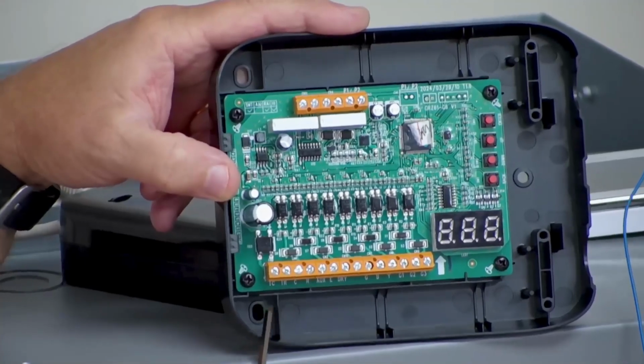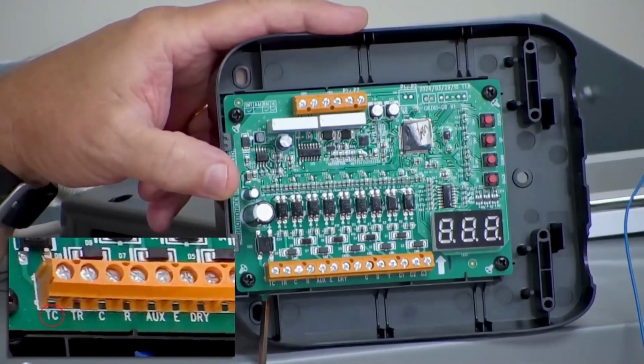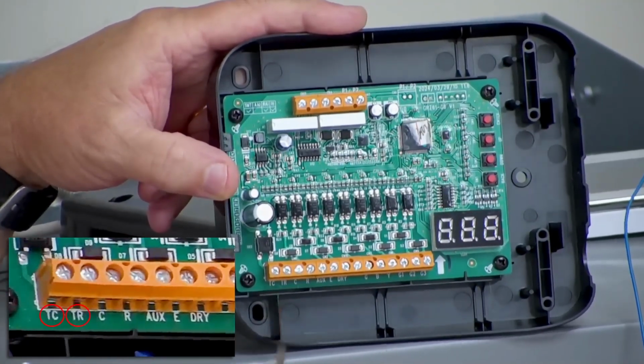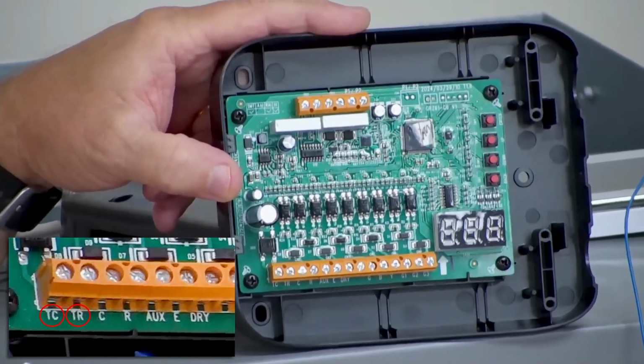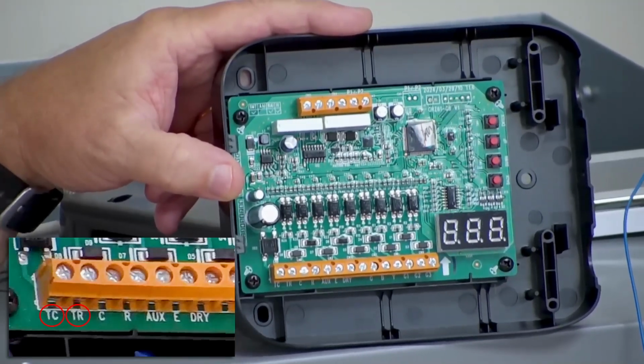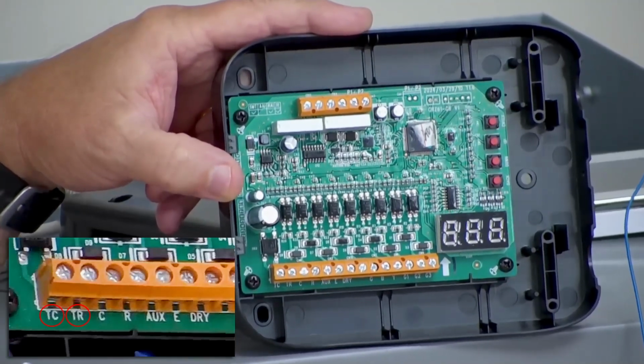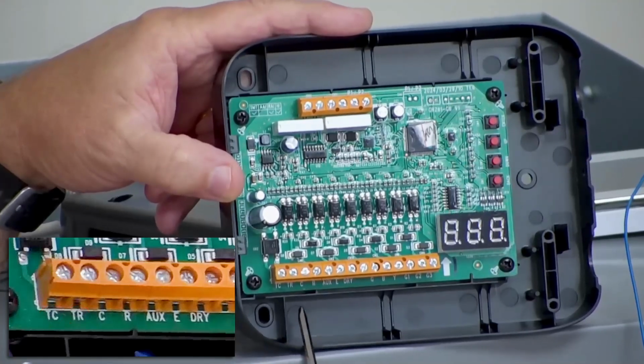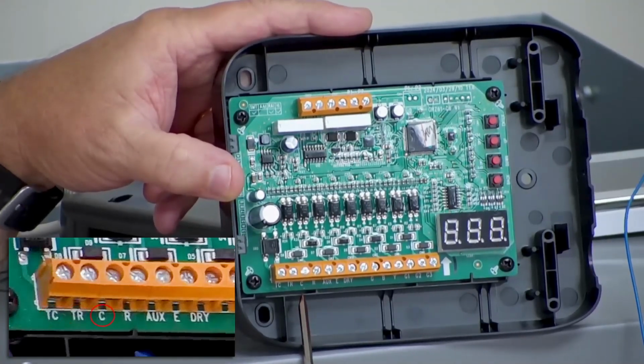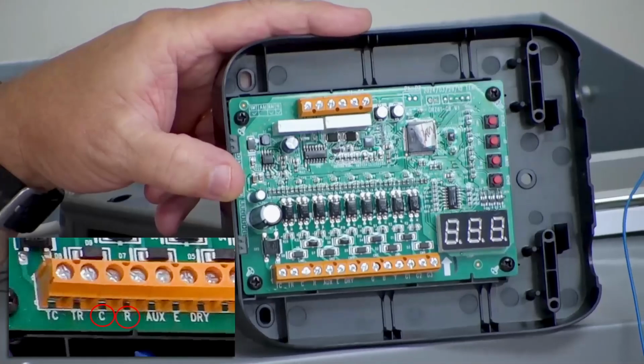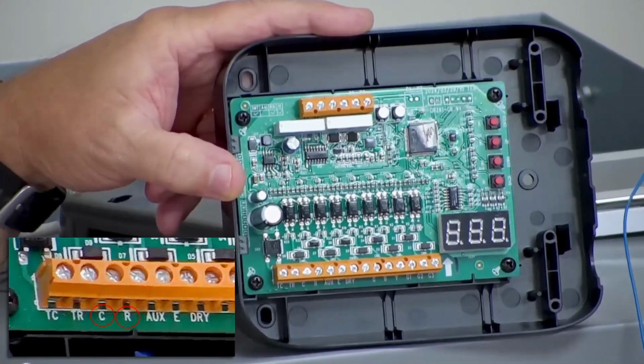and that's going to be your power supply for 24 volts for the 24-volt adapter. And right here on this 24-volt adapter, you've got a TC and a TR. So that is your transformer common and your transformer hot, which is the R. Okay. Then from there, going to your thermostat, you've got a C terminal, and you have an R terminal. That's going to give you your power to your thermostat.